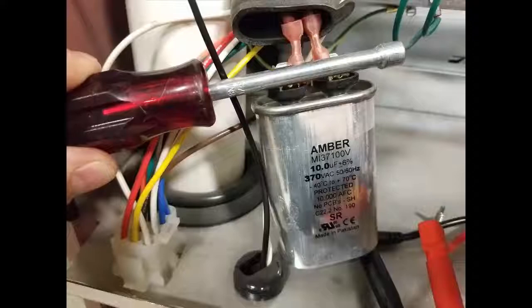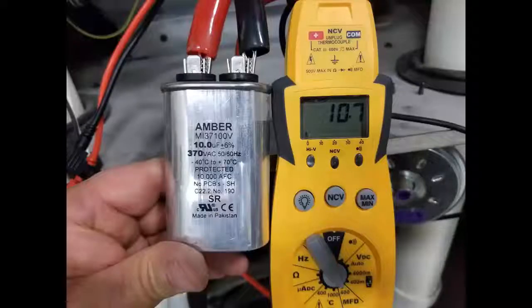I set my meter to microfarads or MFD, and I measure the capacitor. Note the capacitor is marked with how many microfarads it should be. In this case, this one is 10. You should be no more than 10% different from what the capacitor is rated. If your reading is more than 10% different, then you need to replace the capacitor. That means it's either bad or going bad.